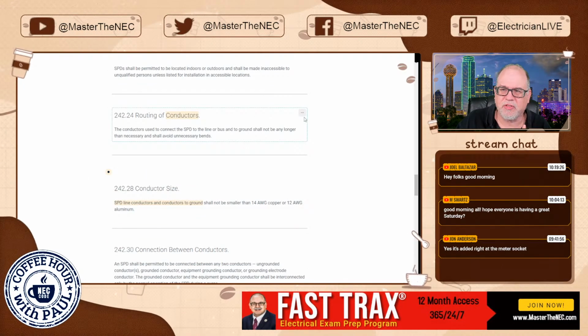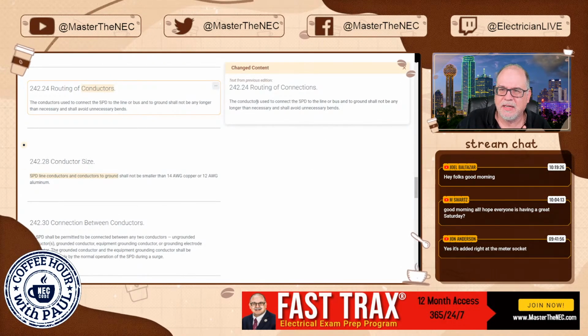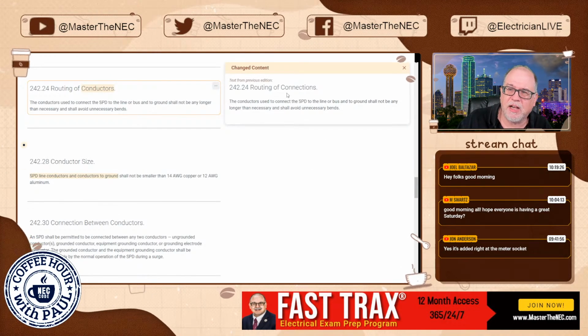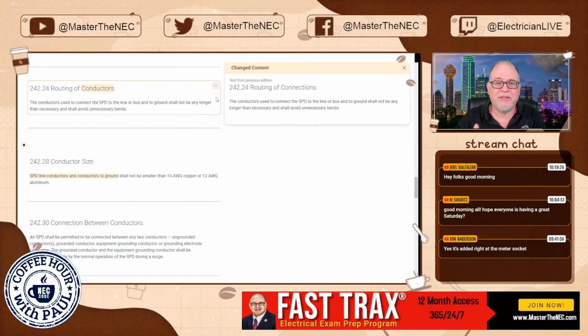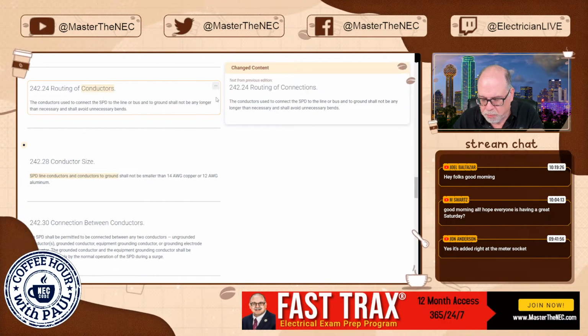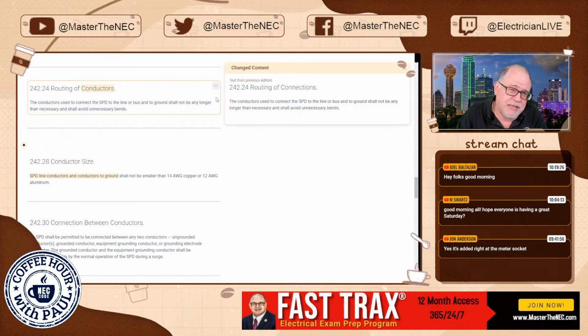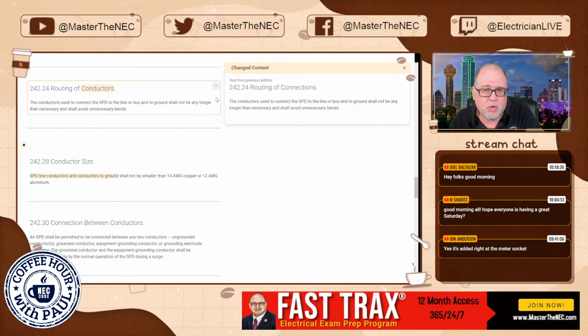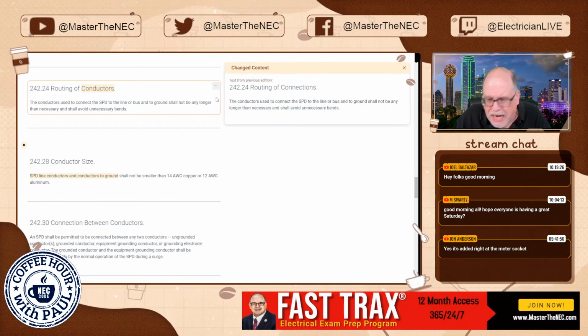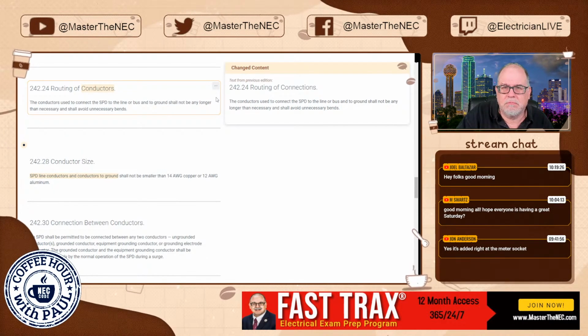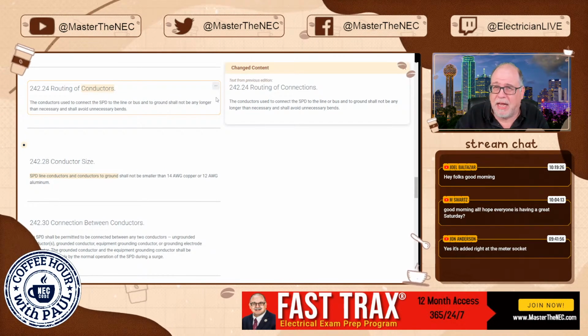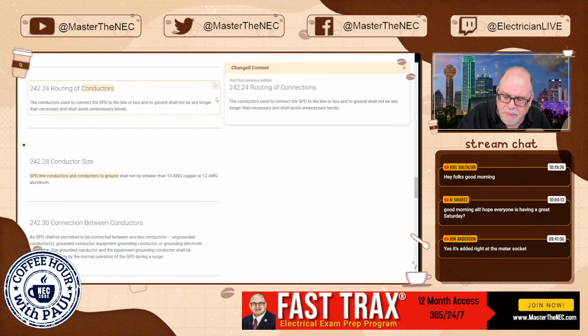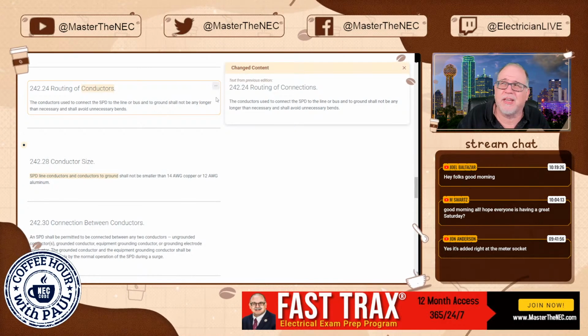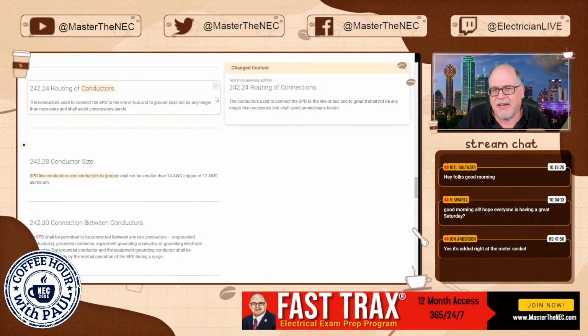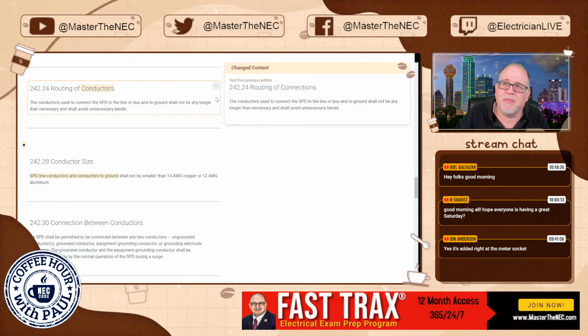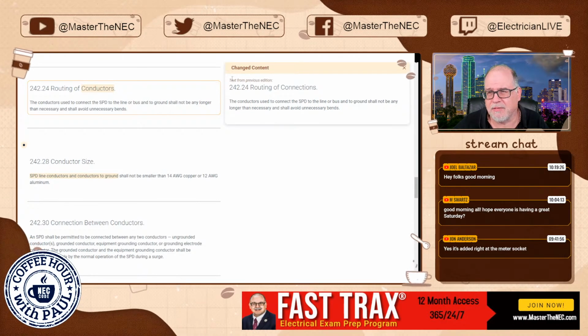Routing of conductors. Let's see, what did it say previously? Previously it says routing of connections. Well, what are we talking about? We're talking about these surge protective devices when you connect them, more importantly the ones that you might do adjacent to the panel, and how you route those. Because you want to keep them as short as possible. The more you loop them around, you can come into something like a choke effect, and that's going to diminish the effectiveness of a surge protective device, right?